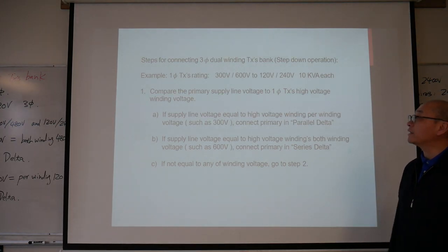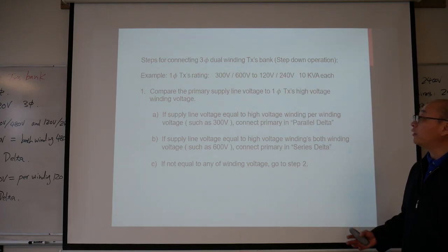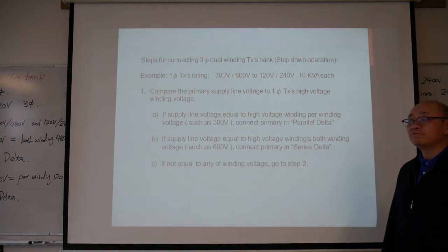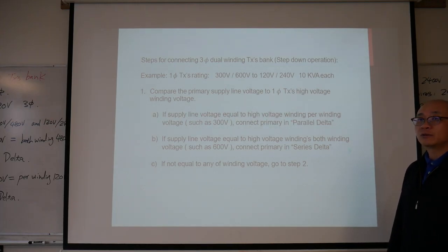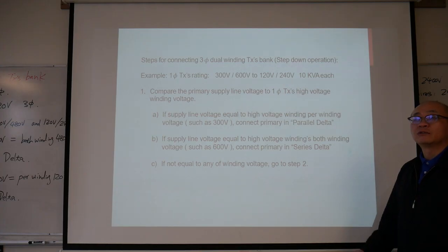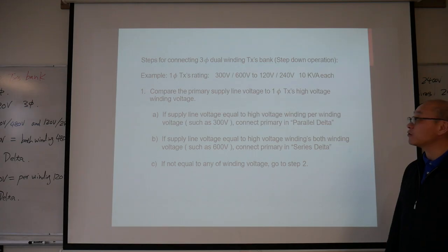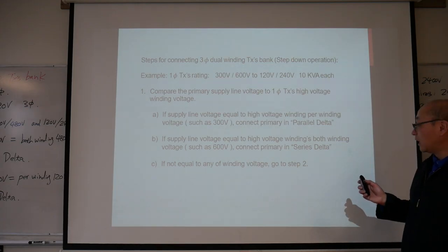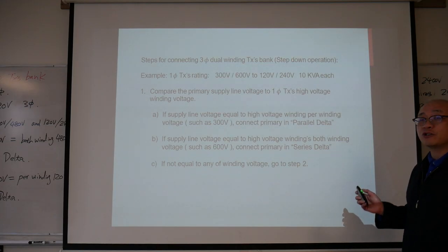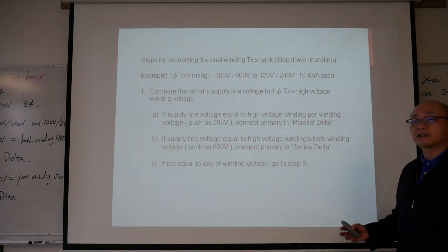I give you a single phase transformer for each of them inside the three-phase bank. It's rated for 300 volt, 600 volt, and the low voltage winding will be 120 volt, 240 volt. So first, you're going to compare the primary supply line voltage to the single phase transformer's high voltage winding voltage. In here, it's a step down operation. If it's a step up, you're just going to compare to the low voltage winding.